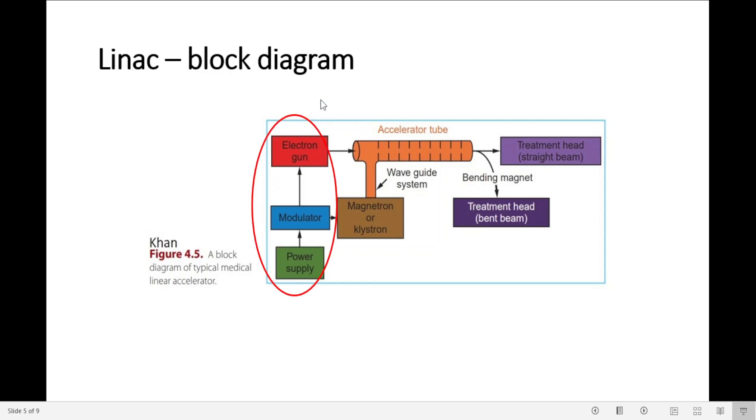So let's focus on the left side here. We have a power supply, a modulator, an electron gun. The power supply provides DC power to the modulator. The modulator delivers high voltage pulses to the electron gun and to the high power oscillator system, which is this one here. The electron gun produces the electrons to be injected into the accelerator tube.